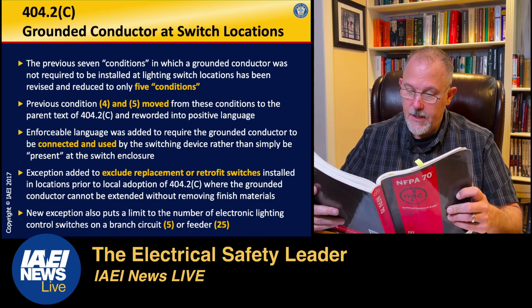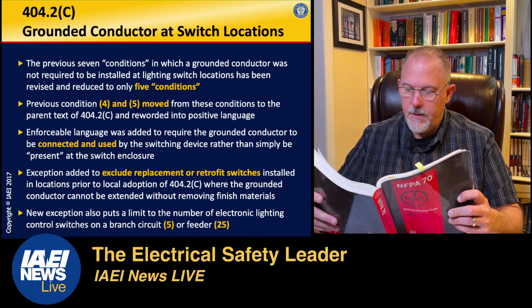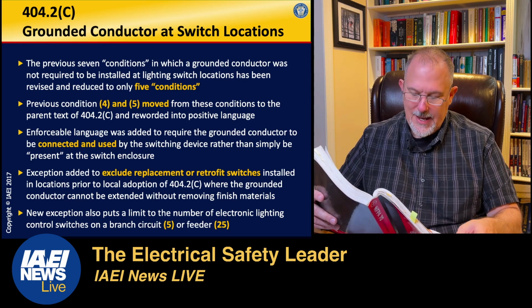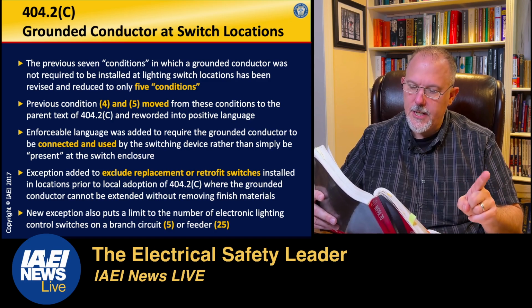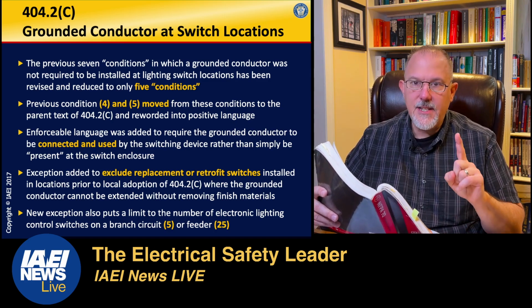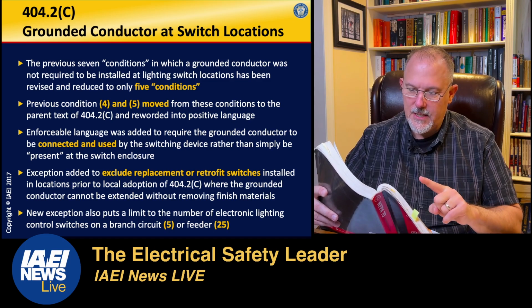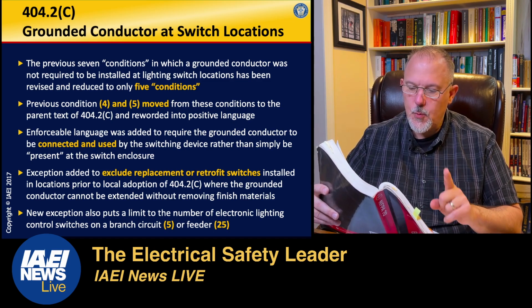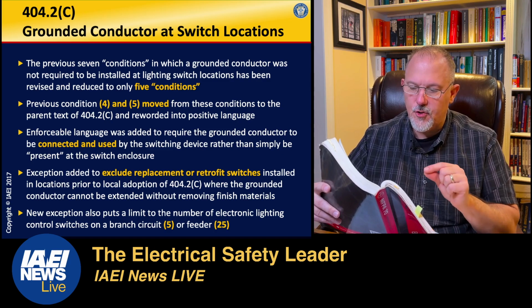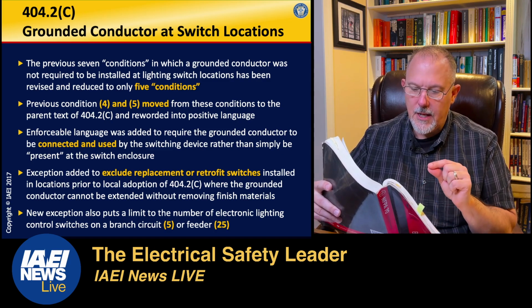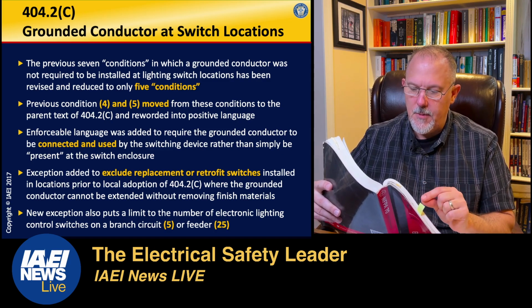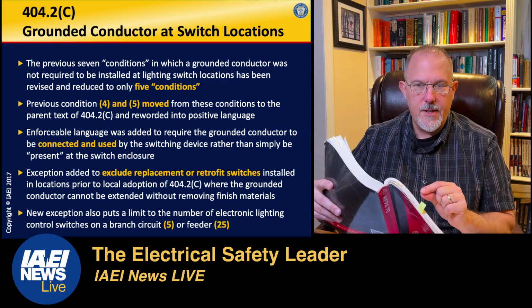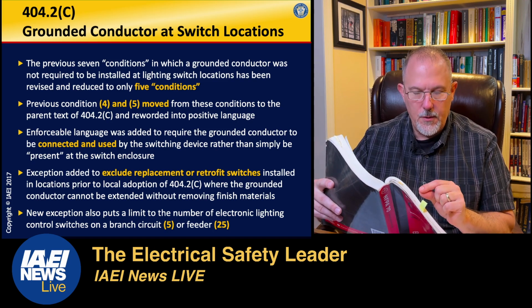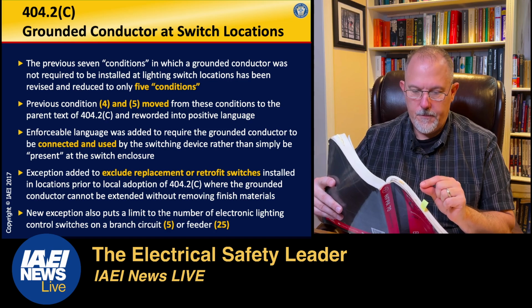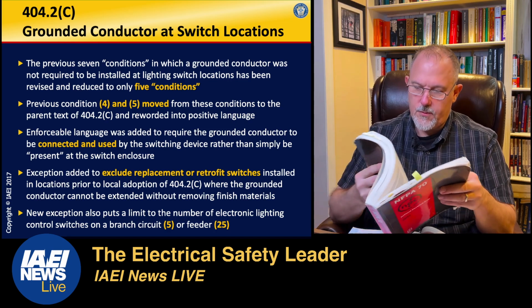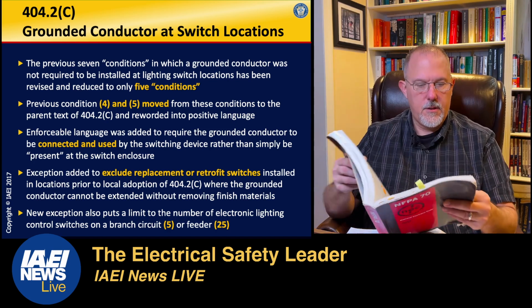There it is. It's in the exception. The connection, so they added this text in the 17. The grounded conductor shall be extended to any switch location as necessary and shall be connected to switching devices that require line to neutral voltage to operate the electronics of the switch in the standby mode and shall meet the requirements of 404.22. What's 404.22? Let's go look at that.